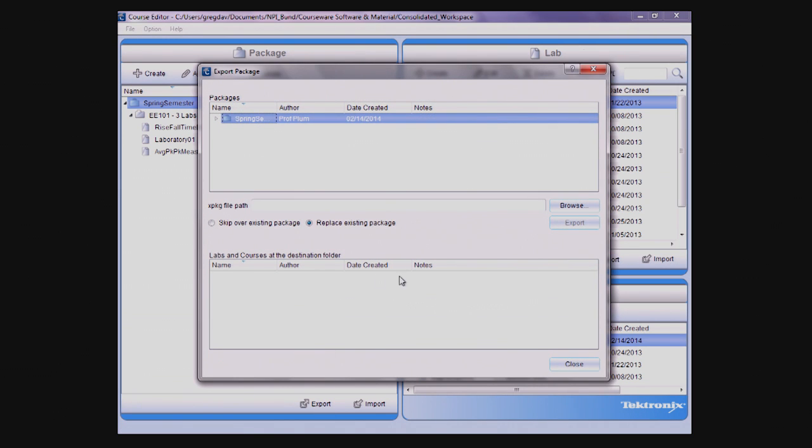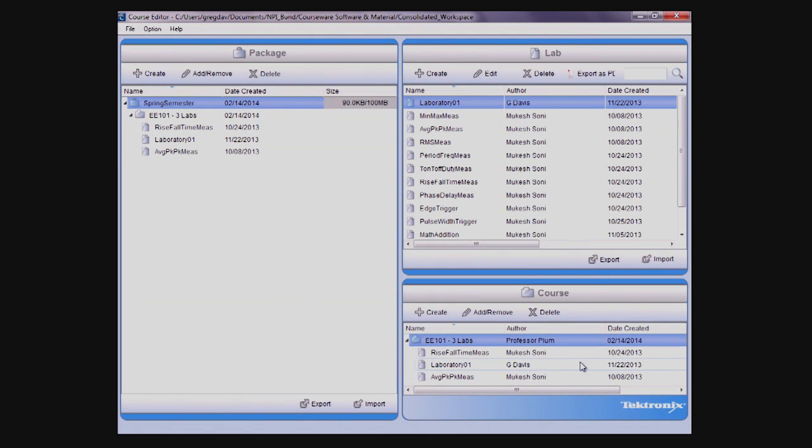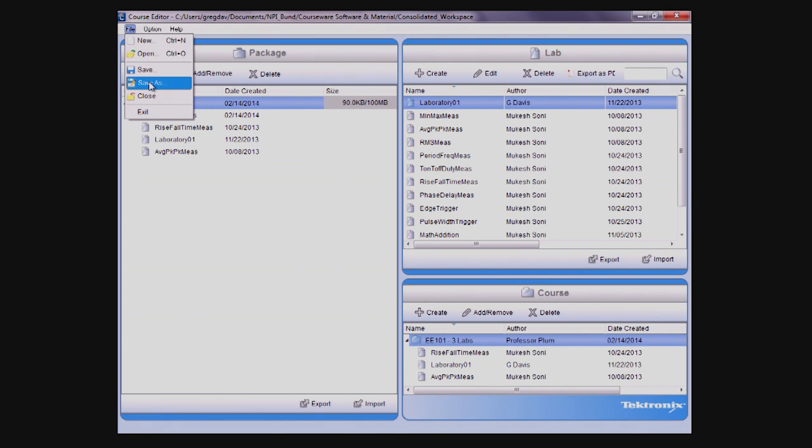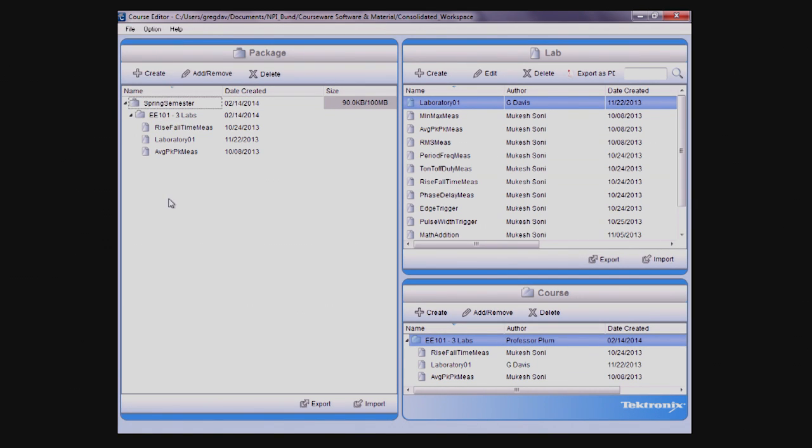When completed, simply export the package to a USB drive and then plug the drive into the USB port on the instrument. You can also save the entire workspace area onto your computer by using Save As in the File menu. This creates an XWSP file that can be reopened at another time for additional editing or sharing with another user.